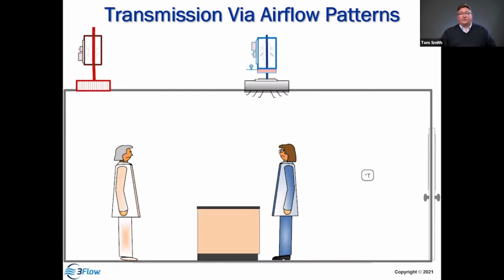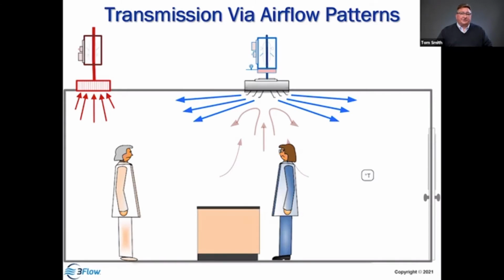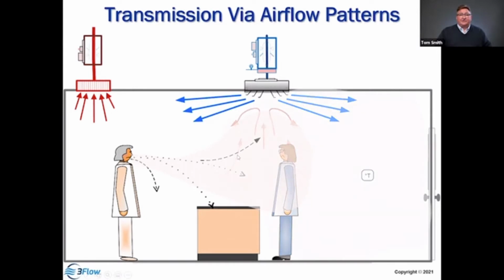So we look into a laboratory and we realize that airflow patterns become very important. So we have maybe a sick person infected in the lab or in a healthy person in any space. And if we look at the airflow patterns within that space and the operation of the supply and the exhaust, in this particular example, we've got air supply that's mixing the air up in the space. So as a person starts to exhale, some of their effluent may come out as droplets, and that heavier material will have a tendency to settle, maybe on the floor and the surfaces surrounding that person. And generally, they recommend 6 feet to be outside of that general ballistic trajectory. However, if we have an aerosolized component, that starts to move with the air and it starts to spread within the space based on the internal airflow patterns. And so if we look at the effect of the internal airflow patterns, it begins to move those contaminants around the space till eventually the whole space is occupied.